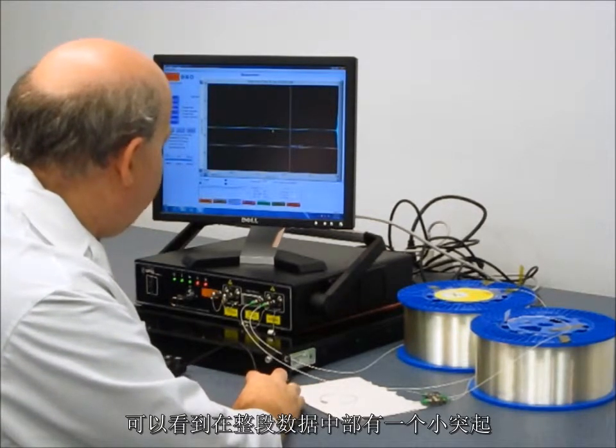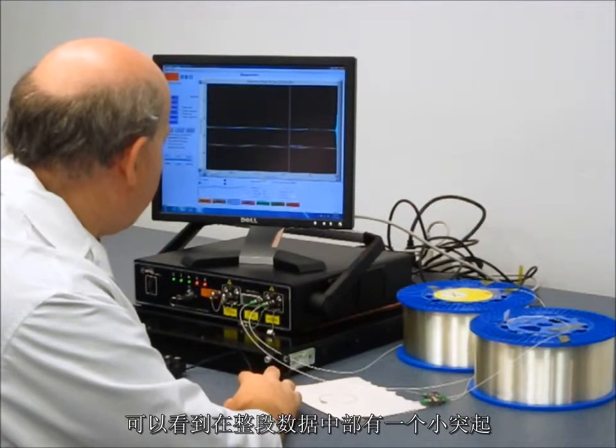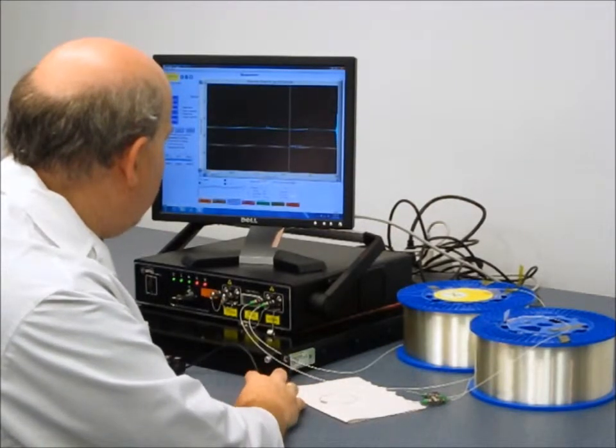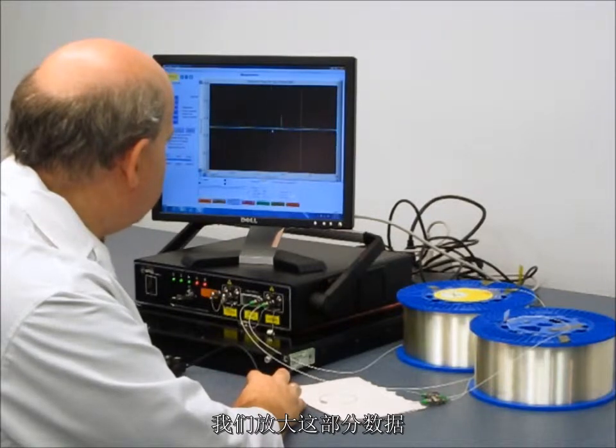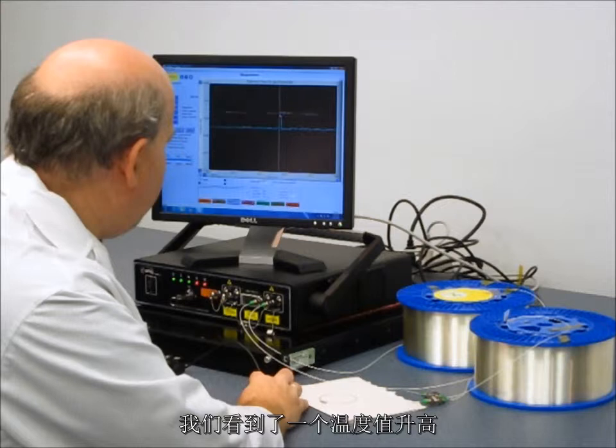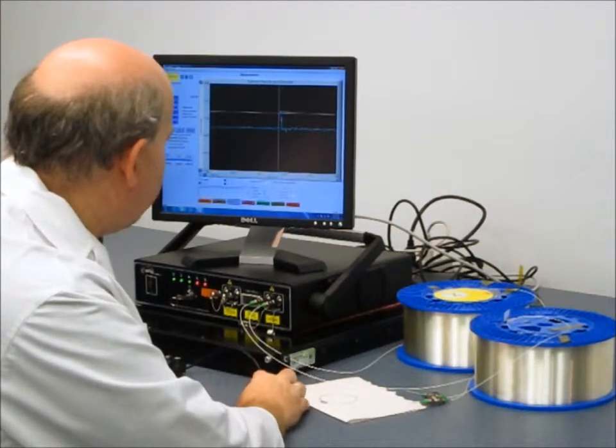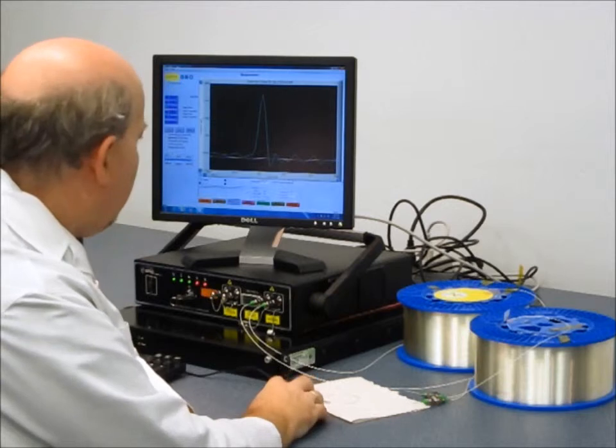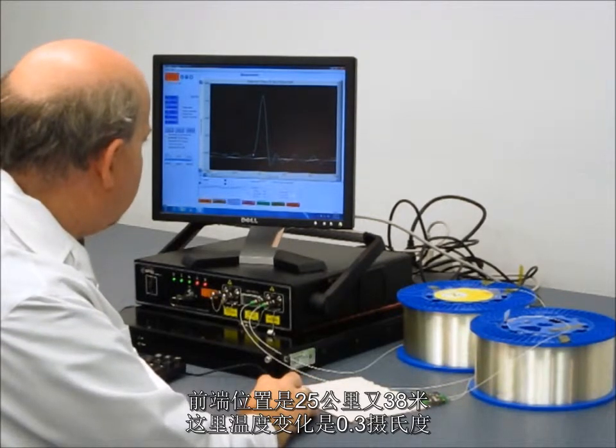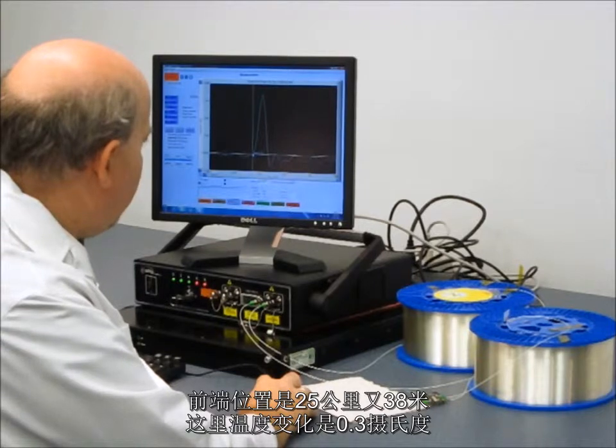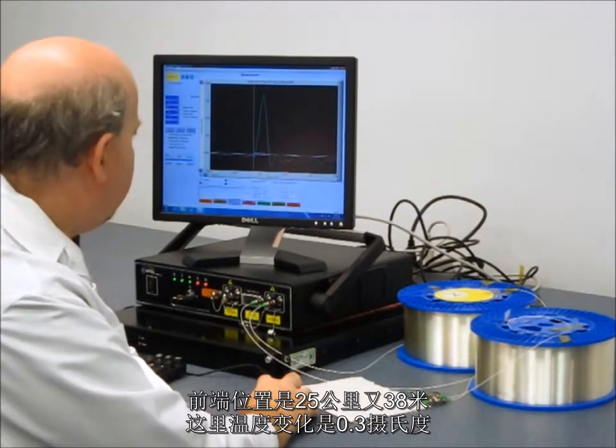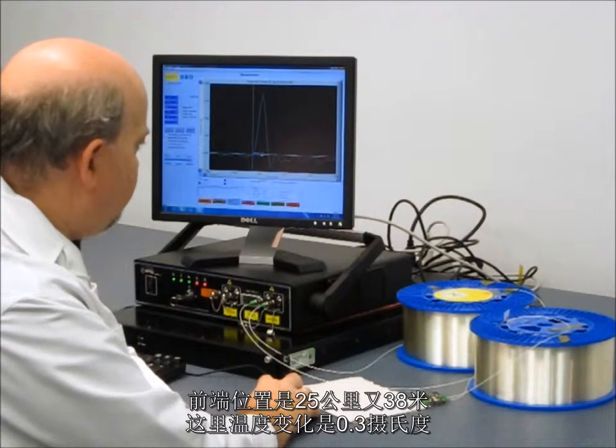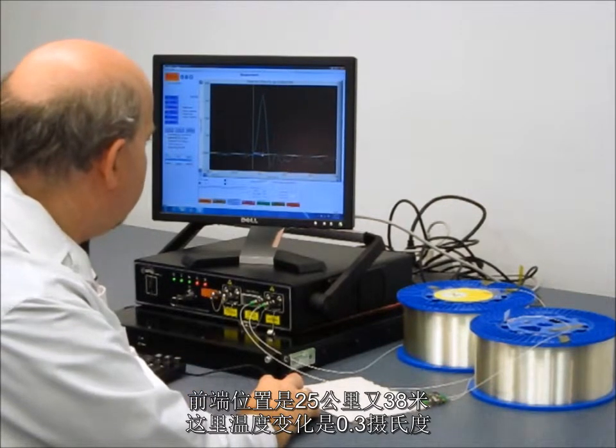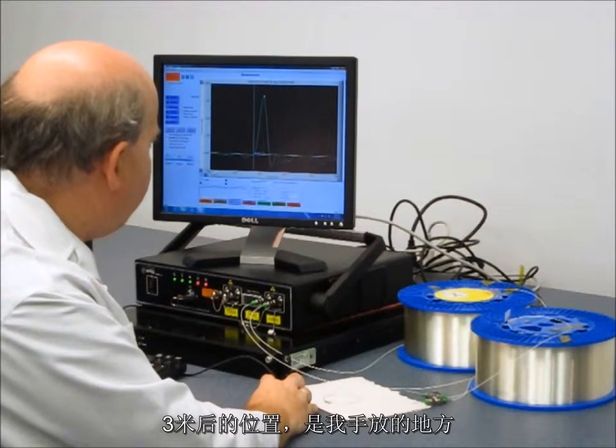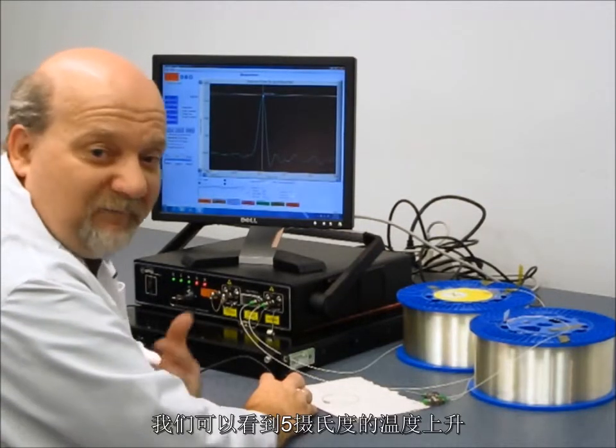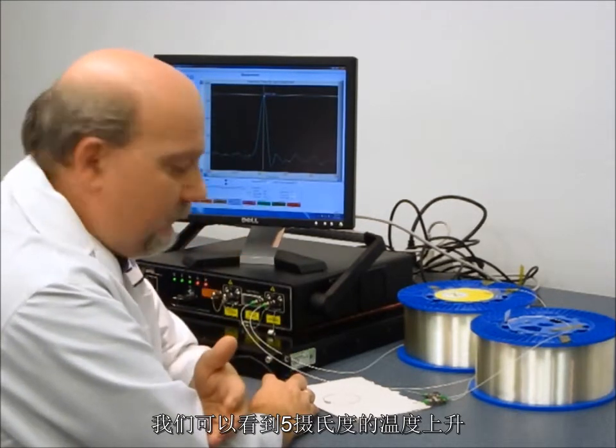So now that we have the data, we can analyze it. If you look carefully in the center of the screen, there's a small blip. And if we engage the zoom, we can zoom in on this region. There's our spike right there. And if we look here at 25 kilometers and 38 meters, we're at our baseline temperature, basically a variation of only about 0.3 degrees. 3 meters up, this is where my hand was, and we see a 5-degree increase in the temperature.